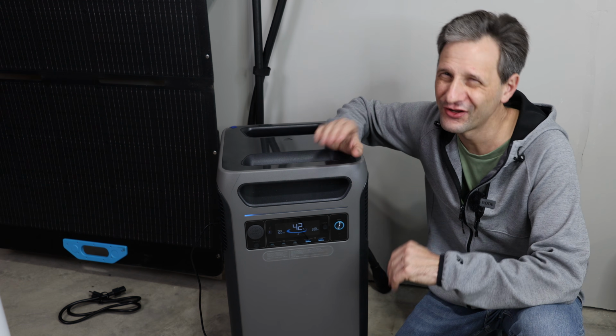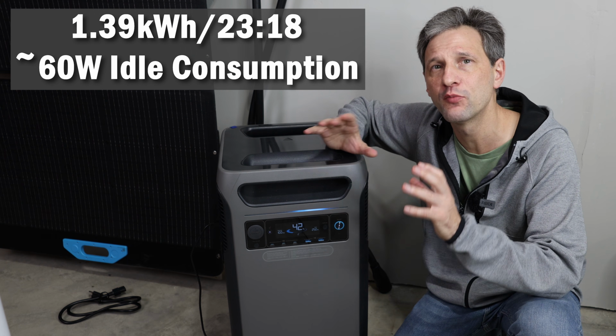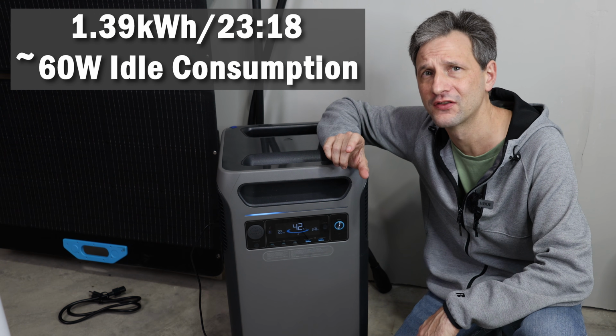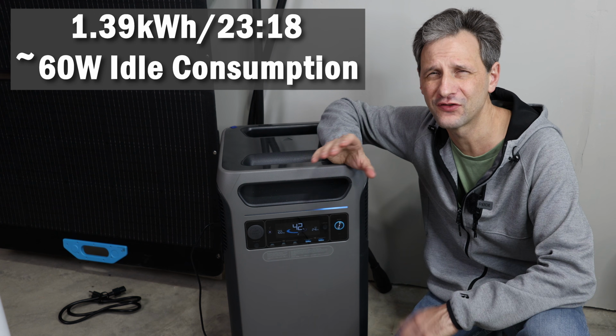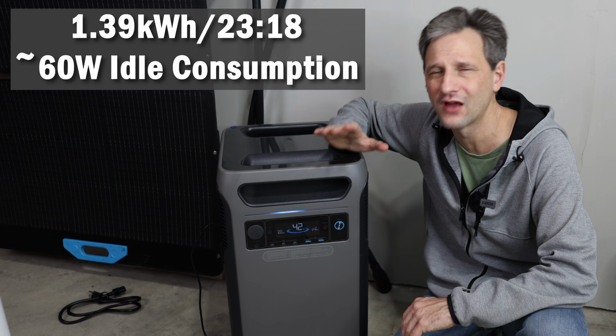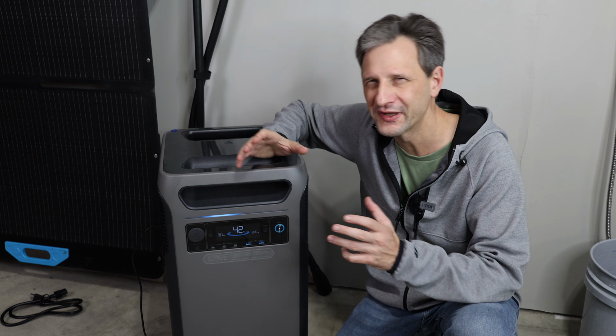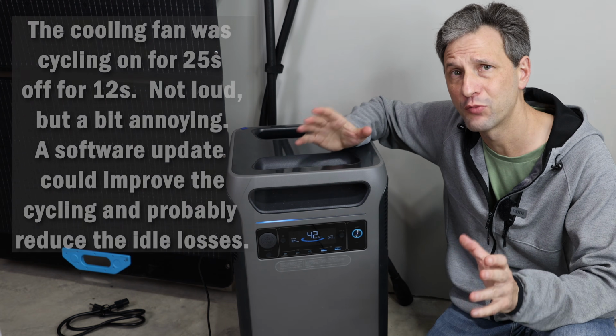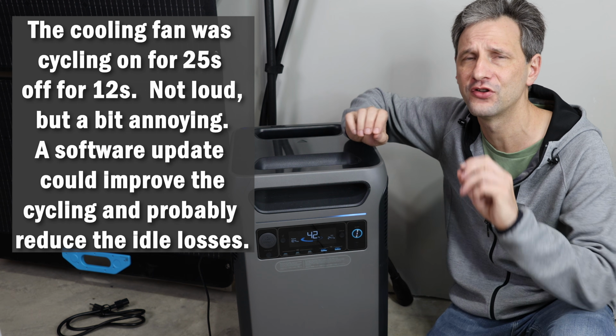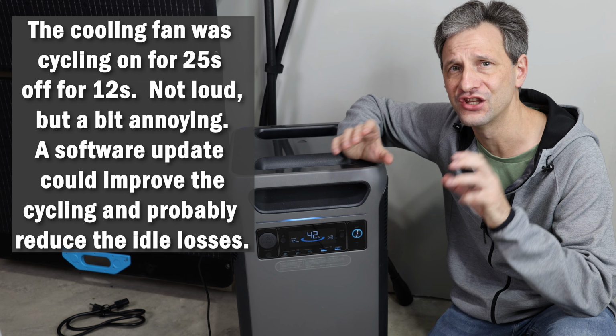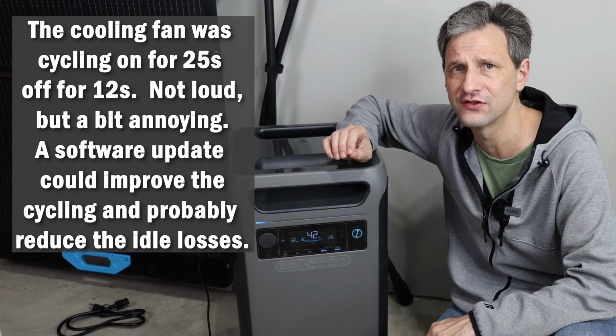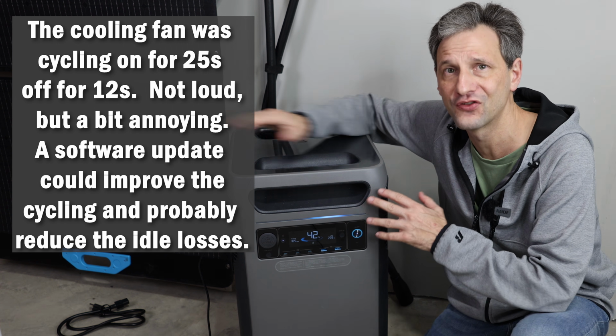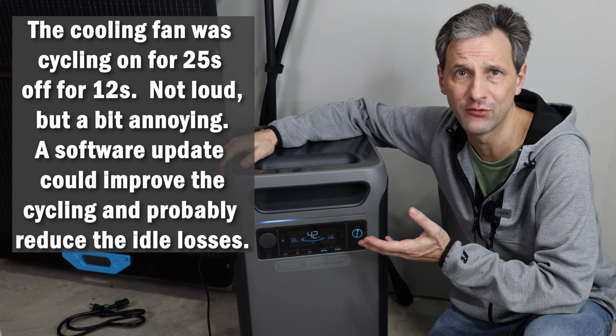That seems like the inverter losses are pretty high. That would amount to 1.39 kilowatt hours of idle loss over the 23 hours and 18 minutes, or roughly a 60 watt idle consumption. Not terrible, but not great either. That's an important characteristic to understand when it comes to determining how much battery capacity you need for a power outage situation, especially if you don't have solar input to help keep the battery refreshed.